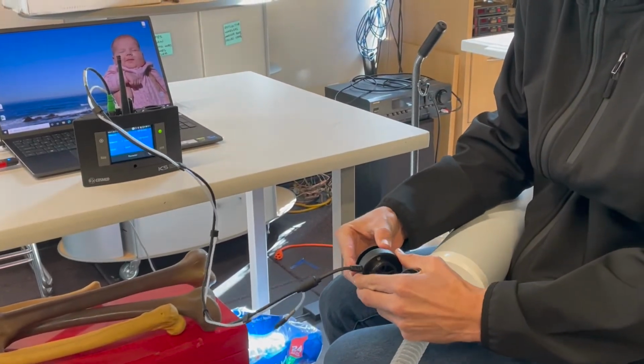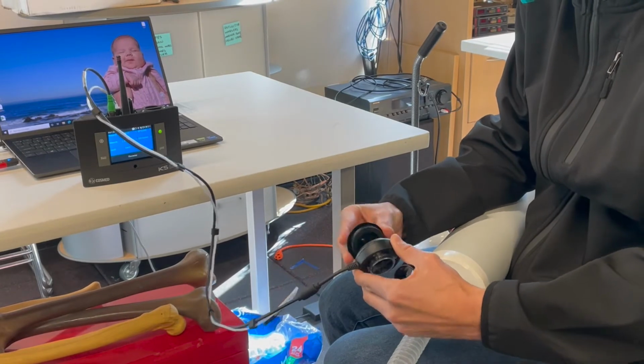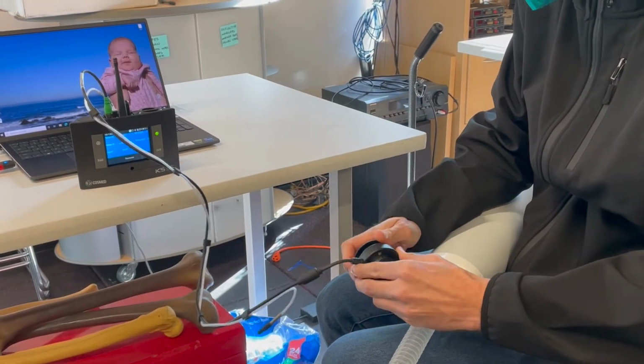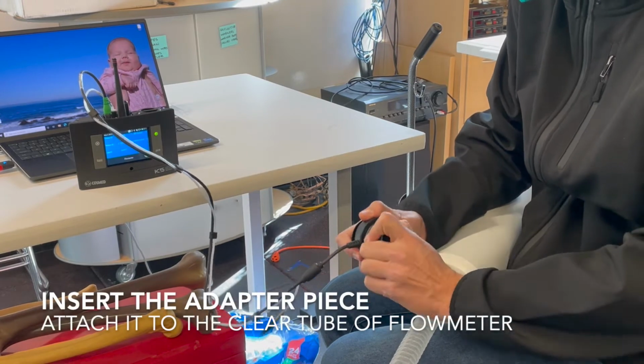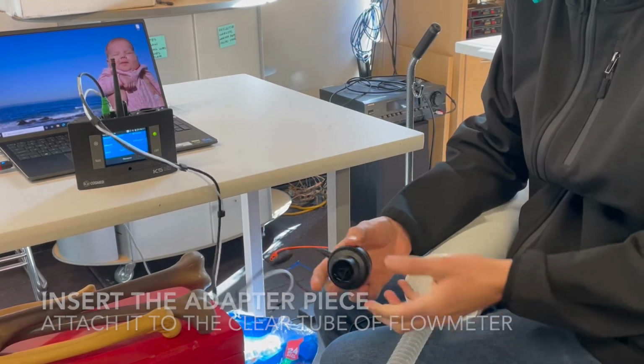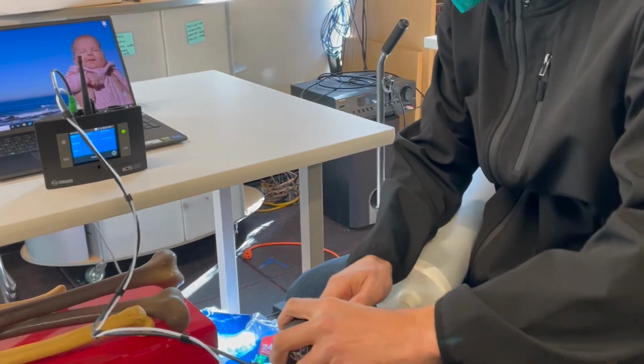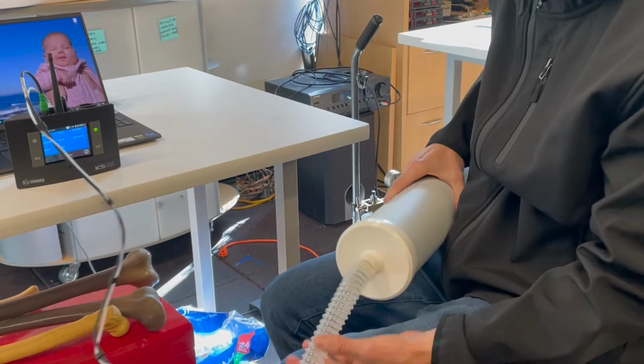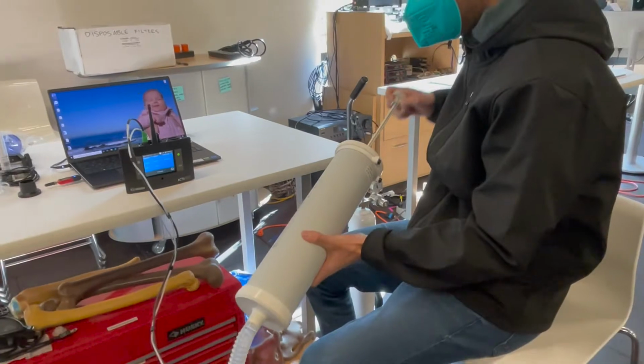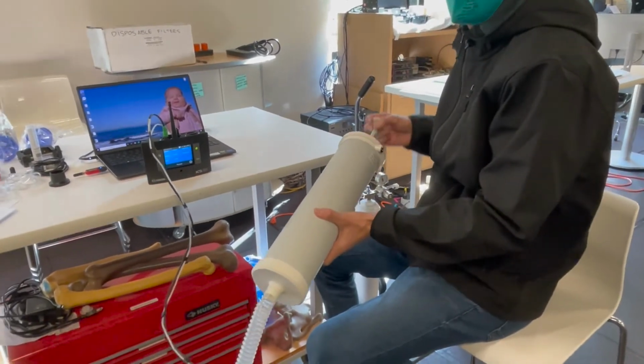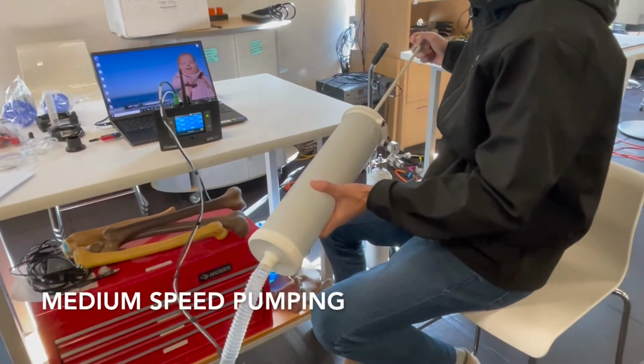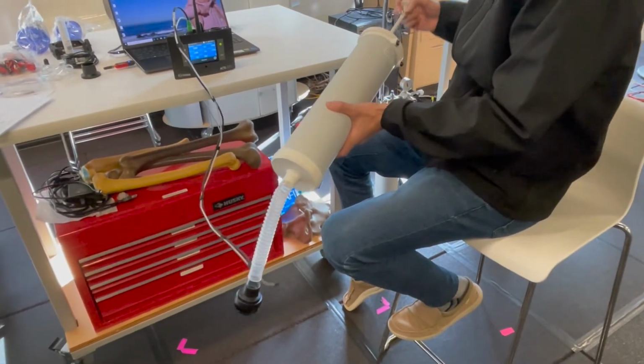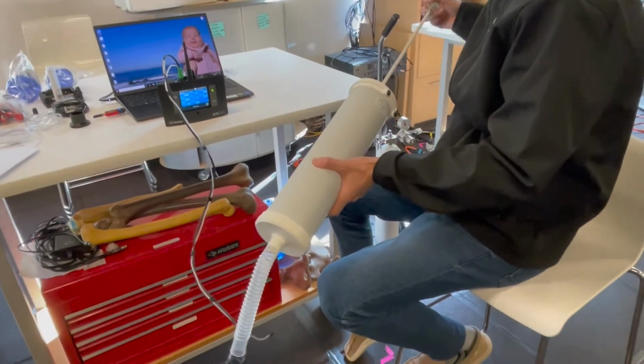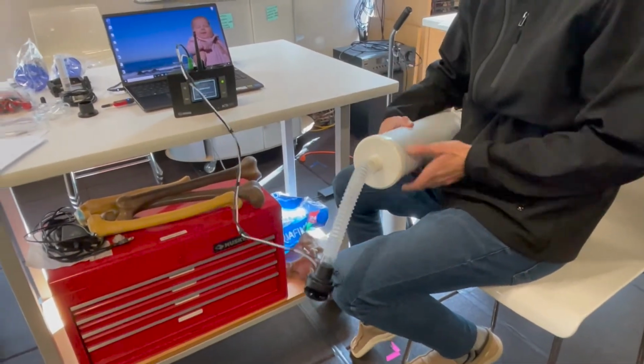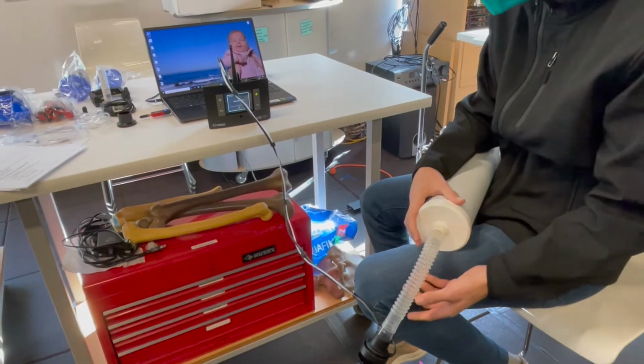This won't fit together nicely unless it's all three pieces. It'll stay kind of loose. Just like that, and like that. Then just go ahead and pump it at a medium speed. These turbines are super linear. With a pneumotach, for example, that would be used on a Parvo cart, you need to hit certain levels of flow because pneumotachs aren't linear in the way they take their measurement.